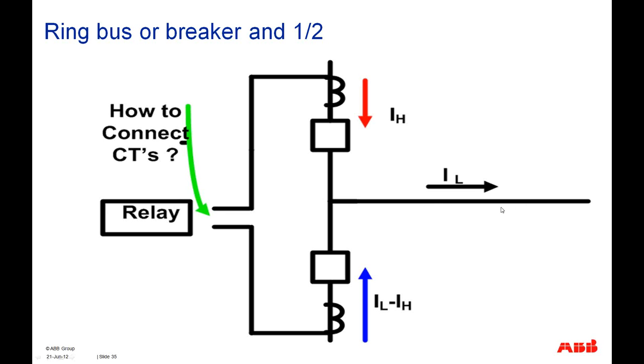That's your transmission line. And if IL is the current of the transmission line, IH is flowing from here, and the rest of the current, IL minus IH, is flowing through this breaker. So there are two CTs which are going to the relays. So the question arises: how should we connect these CTs? One option would be to connect these two CTs directly to the relay and let the relay do the math, or the other way is to parallel these two CTs and then feed the resultant current to the relay.